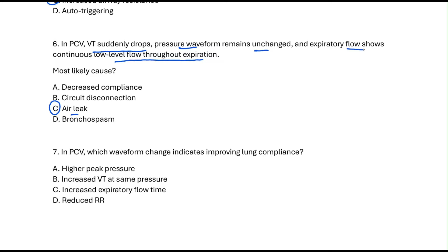So you can see there the pressure waveform remains the same, but it's the expiratory flow that shows continuous low level flow throughout the expiration. So that will be a classic example of air leak.